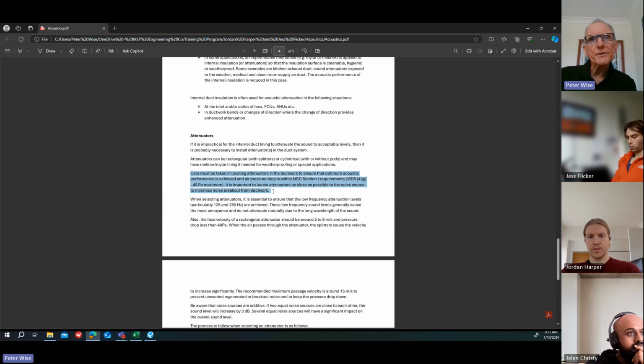So it's important to locate the attenuators as close as possible to the noise source to minimise noise breakout from the ductwork, but beware of fittings. Now, when you're selecting attenuators, going back to that data I just showed you, it's essential to ensure that the low frequency attenuation levels, particularly 125 and 250 Hertz, are achieved. 63 Hertz is given as an insertion loss on the data, but the acoustic consultants have always said, don't worry about the 63. The 125 and 250 are the ones to look at.